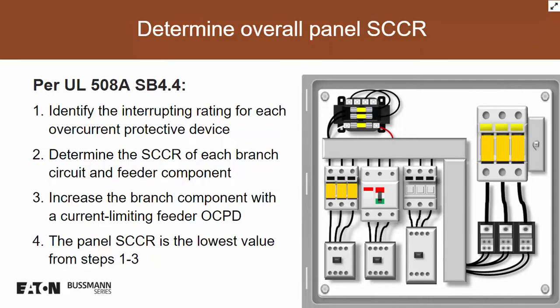Then we move into step number 2 again. Step number 2 is looking at all the components, the feeder components as well as the branch components, with the associated overcurrent protective device, which is the combination rating for those different components. And what is the lowest one I have? So if step number 1 is 65,000 and step number 2 is 10,000, then right now my panel is rated for 10,000 amps SCCR.